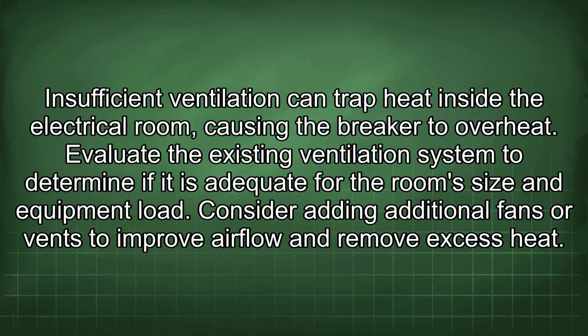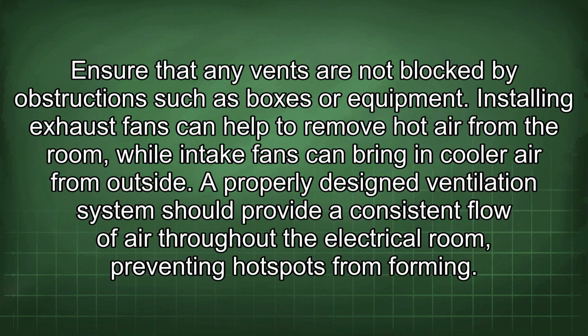Evaluate the existing ventilation system to determine if it is adequate for the room size and equipment load. Consider adding additional fans or vents to improve airflow and remove excess heat. Ensure that any vents are not blocked by obstructions such as boxes or equipment. Installing exhaust fans can help to remove hot air from the room, while intake fans can bring in cooler air from outside.